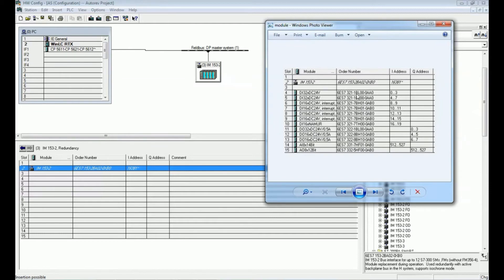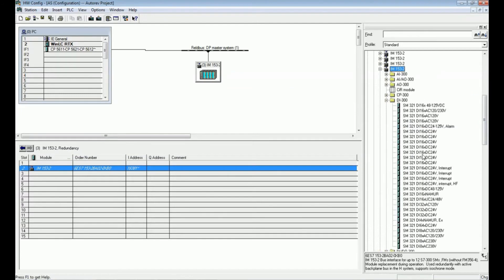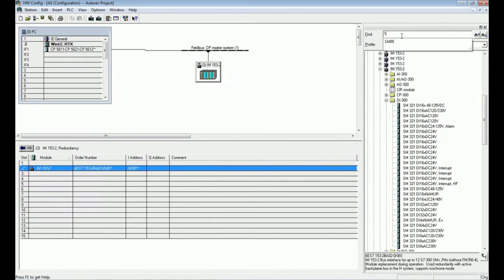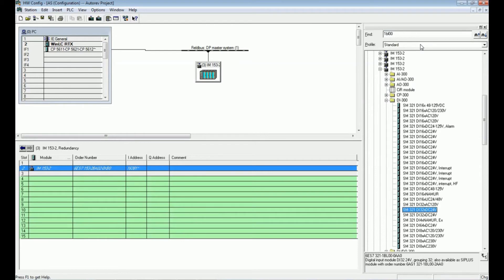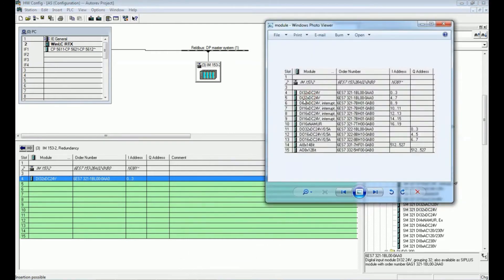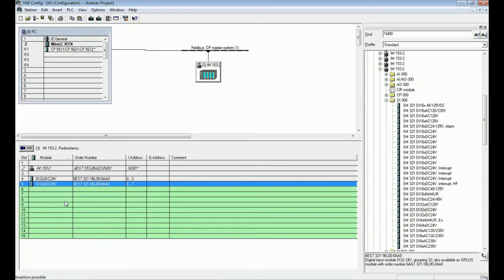The serial number for the first digital input is 1BL00-0AA0. I will search using this order number in the Find window — '1BL00' — and the system finds it easily. I expand the module, open Digital Input, and search for '1BL00'. I then drag and drop it into the rack. Our second I/O is also a 32-bit module with the same serial number, so we can copy and paste it into the rack. Like that we will add all I/O modules.